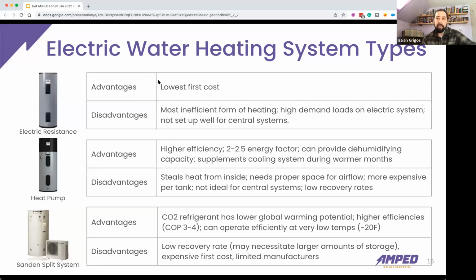So what you end up doing for a multifamily setup is you end up with a lot of storage. Basically you're making a small amount of water over an extended period of time. The way this system works is it has an outdoor condenser unit, like any of the other heat pump split systems, and you run water piping out to it where it heats up the water, and then you pipe it inside. Expensive first cost, very efficient. I think it can operate down to -20, -30 degrees and still make hot water. But for larger multifamily buildings, you might need 8 or 9 of these systems and a lot of storage.